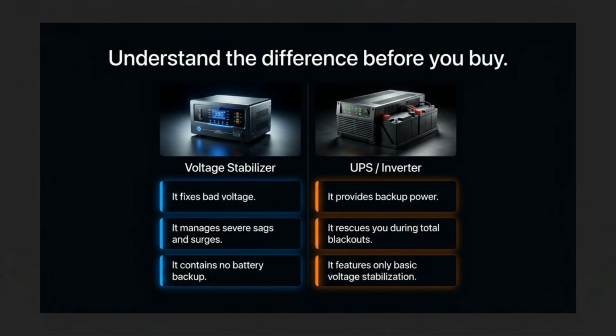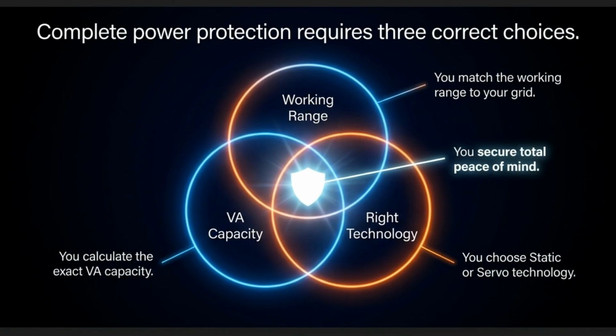Understand the difference between a voltage stabilizer and a UPS/inverter before you buy. A stabilizer fixes bad voltage and manages surges, but has no battery. A UPS provides backup power during blackouts and features only basic stabilization. Complete power protection requires 3 correct choices: matching the working range to your grid, calculating the exact VA capacity, and choosing the right technology. This secures total peace of mind.